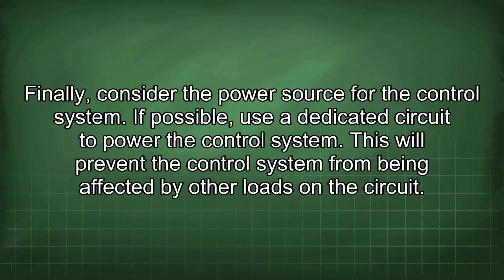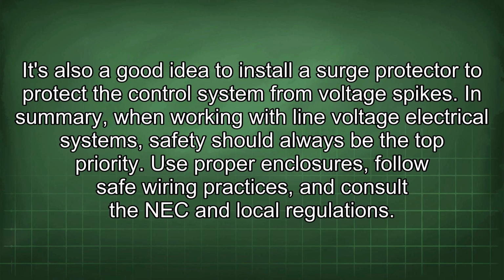Finally, consider the power source for the control system. If possible, use a dedicated circuit to power the control system. This will prevent the control system from being affected by other loads on the circuit. It's also a good idea to install a surge protector to protect the control system from voltage spikes.